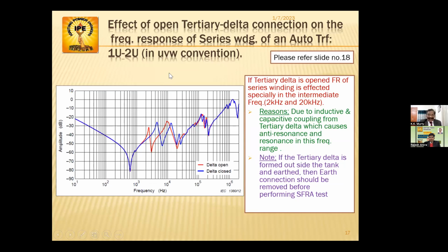Now, tertiary delta open frequency response. Many utilities want the tertiary delta to be open. The tertiary delta is there in most of the auto transformers, and many utilities want that the tertiary delta should not be closed, and they should bring two bushings out at the top of the transformer, which can be closed while earthing it, and for testing purposes they can have the open delta, and the curve of open delta has to be like this.